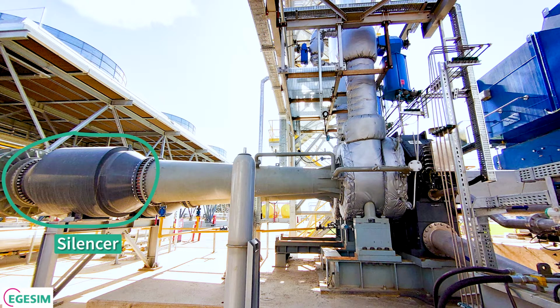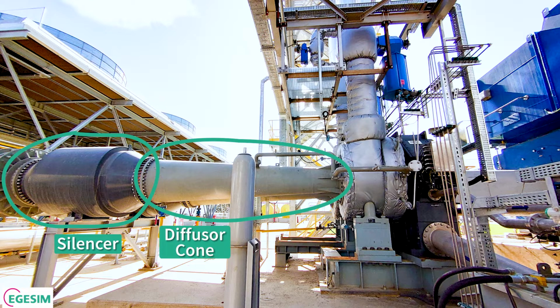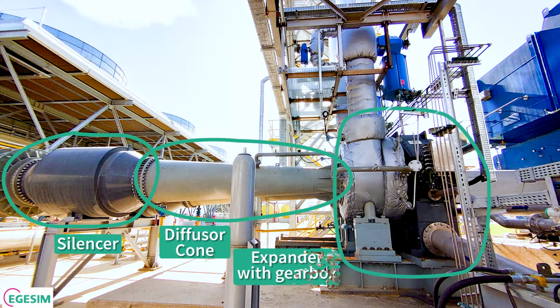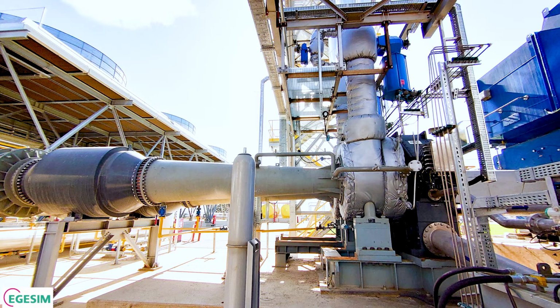Then you see further to the right the so-called discharge cone, which in the end is nothing more than a diffuser, as it's named here, that takes the velocity and turns it into pressure. Further to the right, the expander with the gearbox. In the end, this expander is running at close to 9,000 RPM, and on the low end, it's at 1,500. And here you can see the inlet trip valve. As our machine is equipped with the inlet guide vane technology, this inlet trip valve is nothing more than just an on-off switch and an emergency shutdown device. The power of the machine is controlled by adjusting the inlet guide vane mechanism.